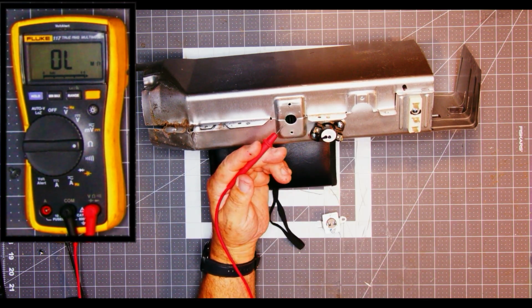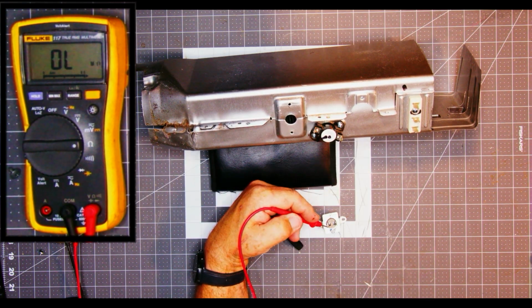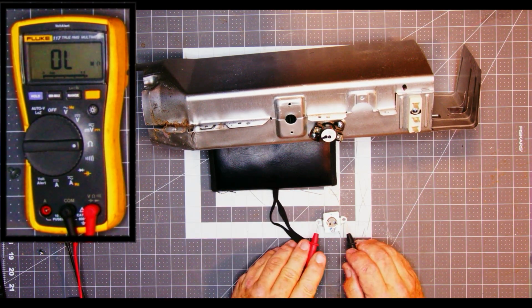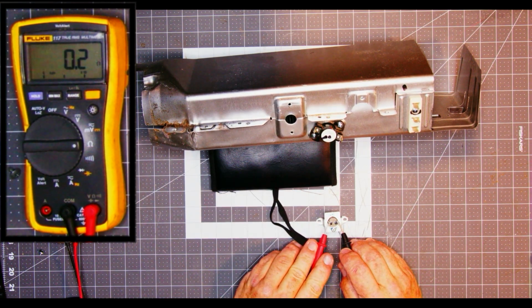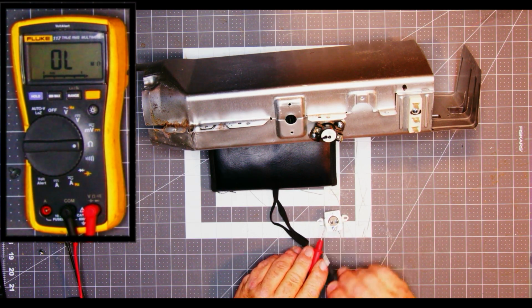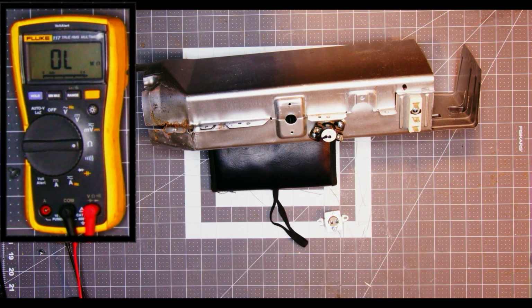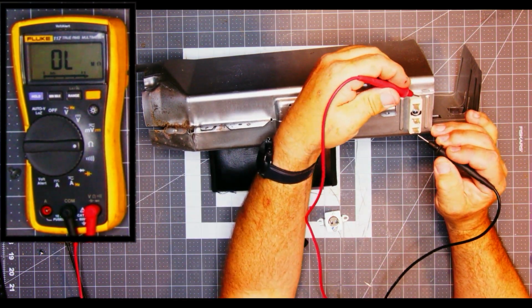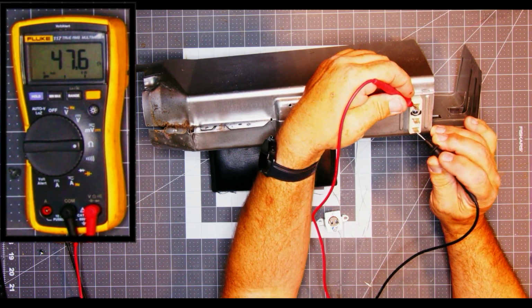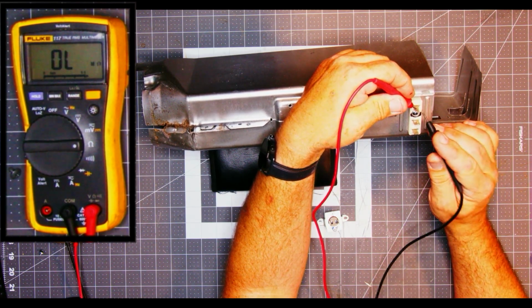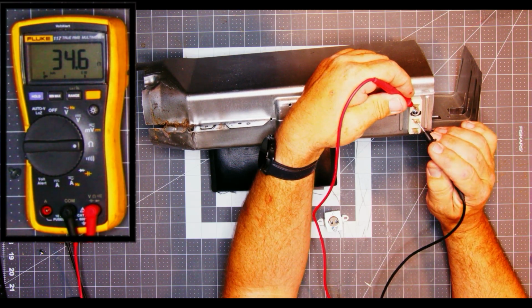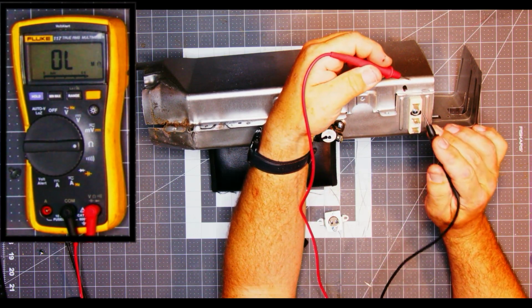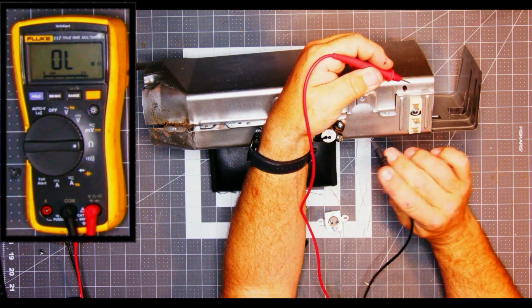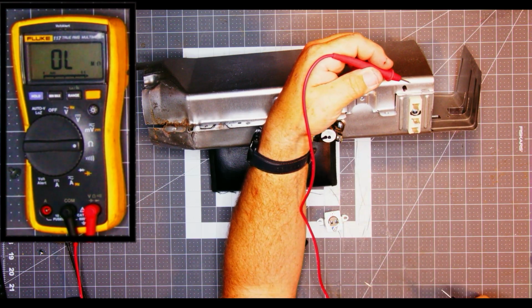The thermal fuse on this unit had failed, but I have a spare. If we measure from one end to the other, we can see that it's reading almost a dead short. That's a good fuse. If we measure from end to end, we can see 47.6 ohms. If we measure from the center tap to the end, we can see 34 ohms. This heater has a high and a low setting, but both of those are properly within spec.